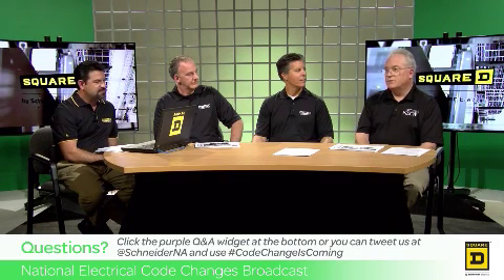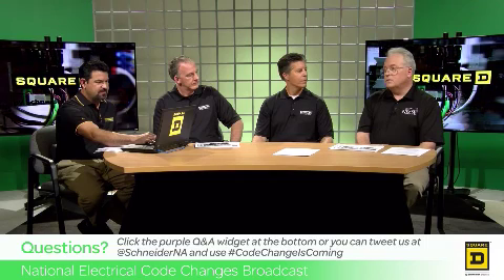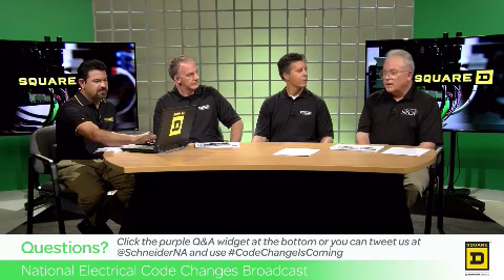Next question is, do the requirements for a wire-type equipment grounding conductor in a rooftop raceway apply to EMT or all metal conduits? That's a good question. I believe the phrase used within the section is metal raceway systems, which would include EMT, rigid metal conduit, intermediate metal conduit, and so forth. And the idea here is if you're using anything other than threaded type fittings, slip fittings, in other words, compression fittings, and so forth, those are more likely and more vulnerable to movement and physical damage that could interrupt an effective ground fault current path. So the answer is it applies to all of those, but it's directly related to the type of fitting that's used in those applications. Okay, great.